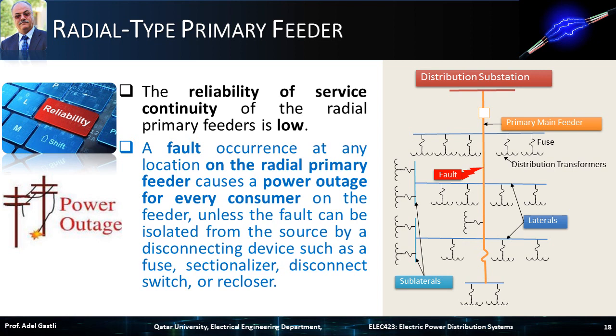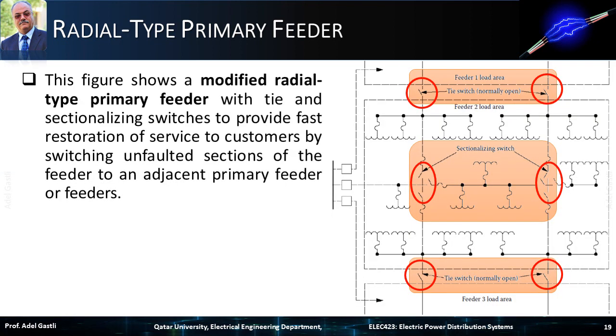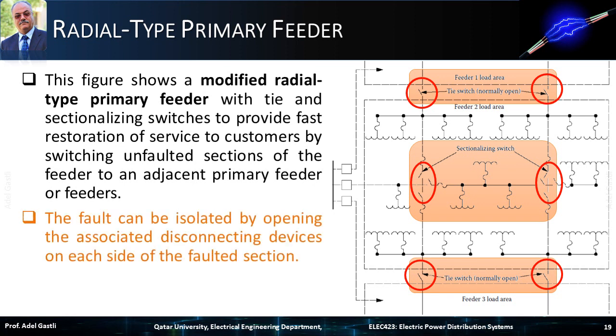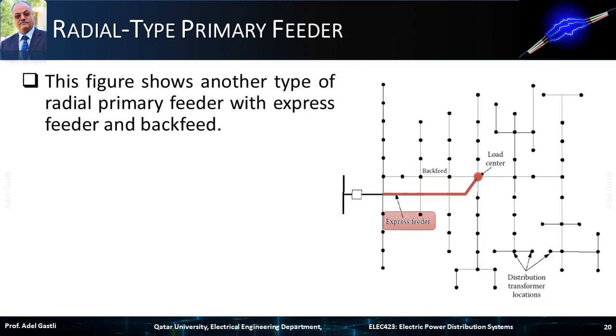This figure shows a modified radial type primary feeder with tie and sectionalizing switches to provide fast restoration of service to customers, by switching unfaulted sections of the feeder to an adjacent primary feeder or feeders. This configuration is much more reliable than the previous one because it can provide better continuity of service. The fault can be isolated by opening the associated disconnecting devices on each side of the faulted section. This figure also shows another type of radial primary feeder with express feeder and back feed, where each dot represents a load lumped at that location.